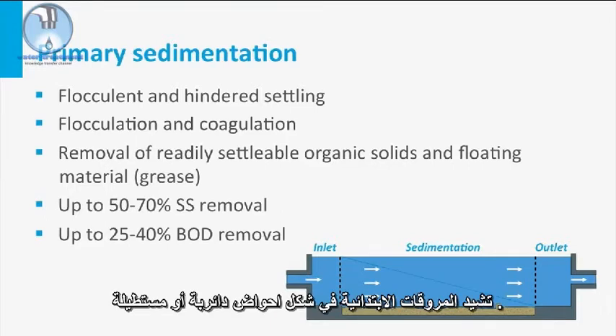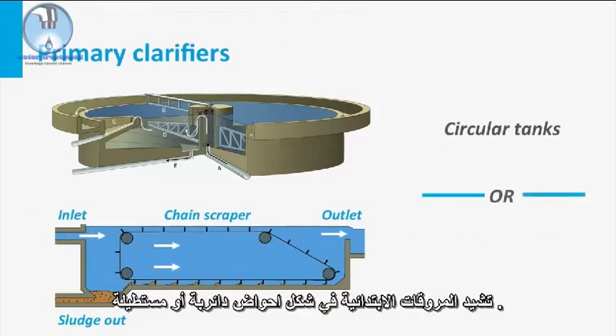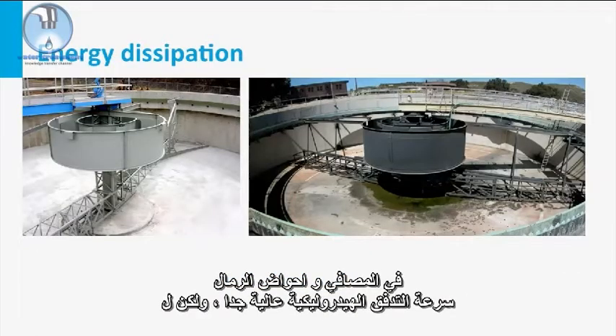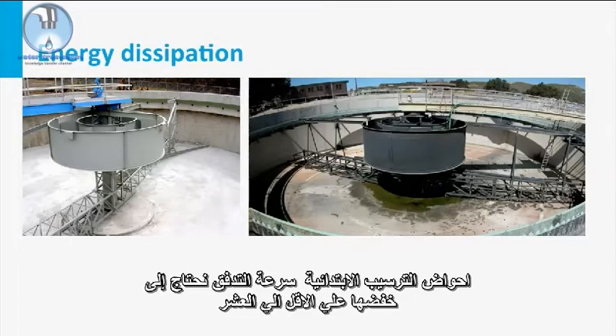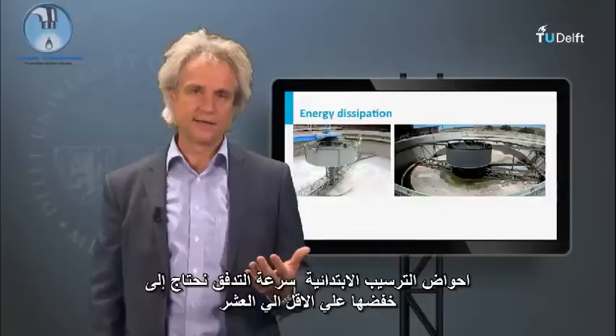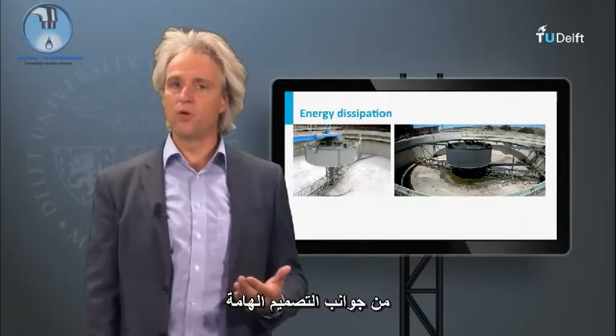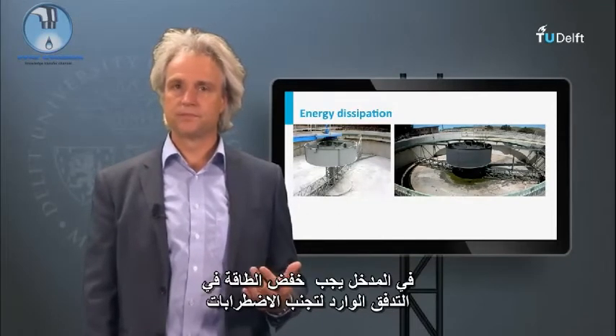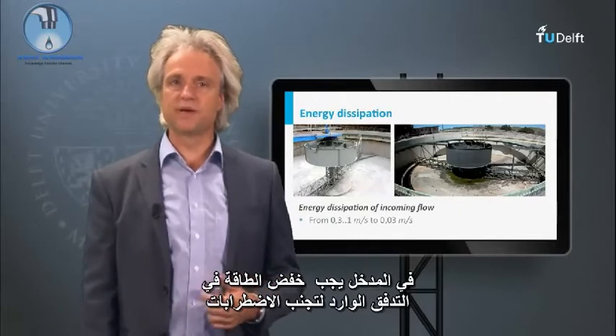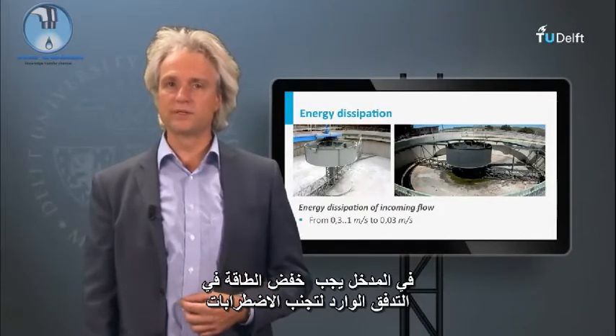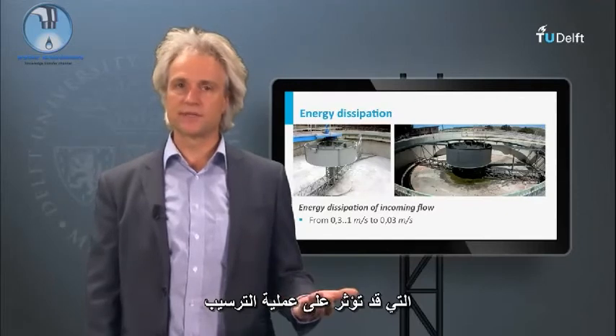Primary clarifiers are constructed in circular tanks as well as in rectangular tanks. In screens and grit chambers, the hydraulic flow velocity is very high, but for the primary settler, the flow velocity needs to be reduced by at least a factor of 10. Therefore, the inlet works and flow distribution of the incoming flow into the clarifier are important design aspects. At the inlet, energy dissipation of the incoming flow is required to avoid turbulence that might affect the settling process.